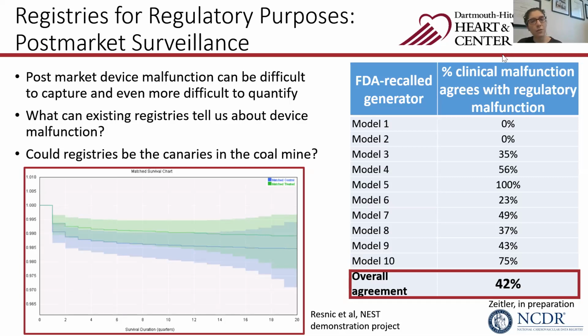And then in a different way, along with some colleagues, some of which are at the Smith Center, we identified generators that were recalled by the FDA in the ICD registry, and identified the reason for recall as indicated by the FDA, and then compared that to the operator reported mode of failure. So when these recalled generators failed, the operator has to report the type of failure that occurred. So we compared those to the type of failure that would be predicted by the FDA's recall, and found that agreement was quite poor at only 42%.